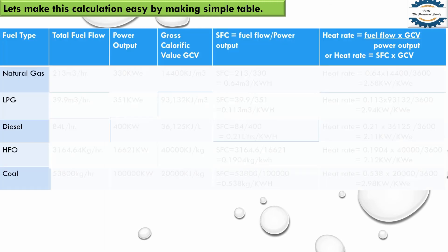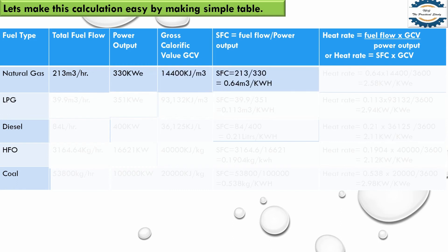To make our calculations simple, let's create a chart. On the left-hand side we have written all the fuels, and we need to find total fuel flow and power output for each fuel power plant. With these two parameters and the gross calorific value, we can find specific fuel consumption and heat rate. Heat rate equals specific fuel consumption multiplied by GCV, divided by 3,600 to convert hours to seconds. For natural gas, we've already done the calculation and are writing it down here.